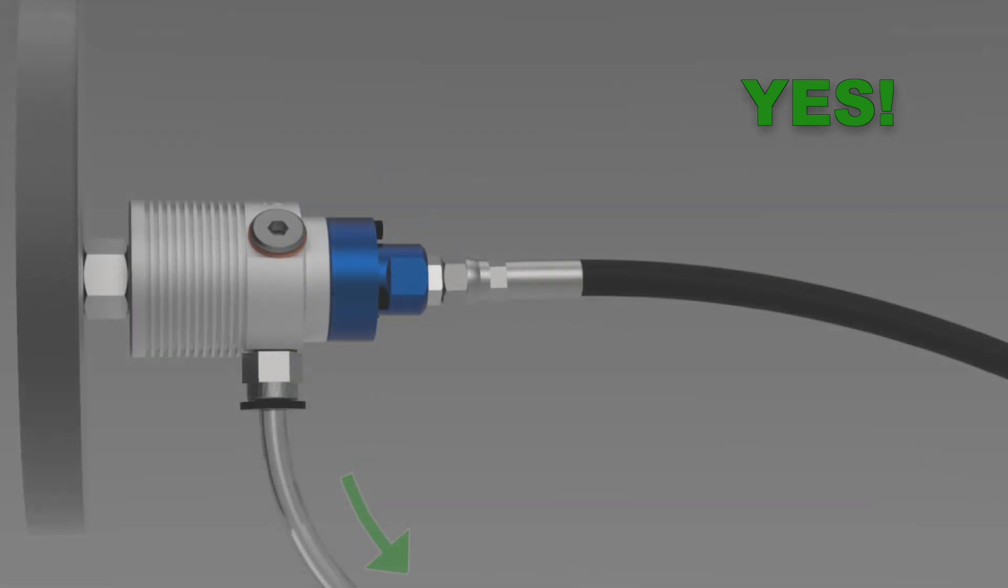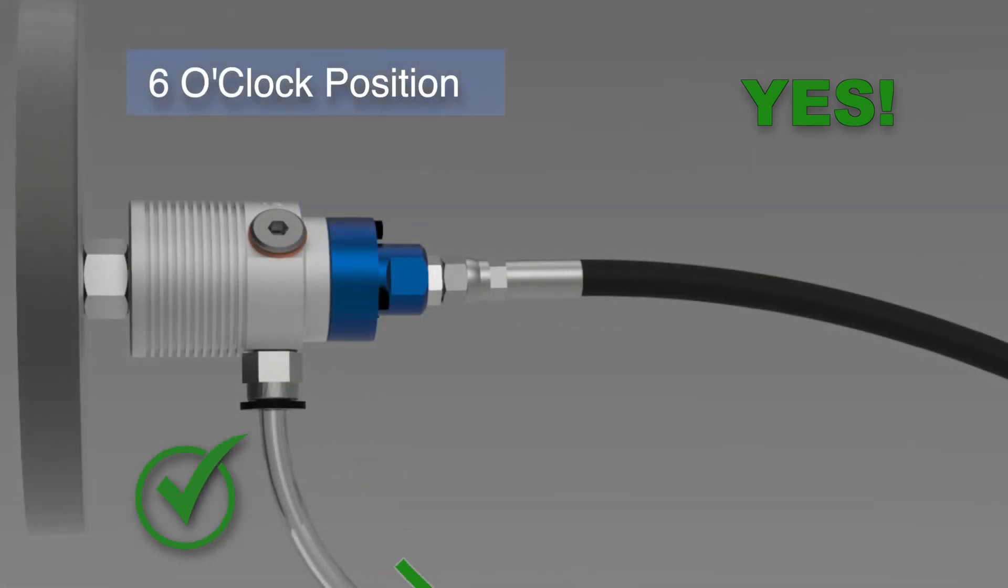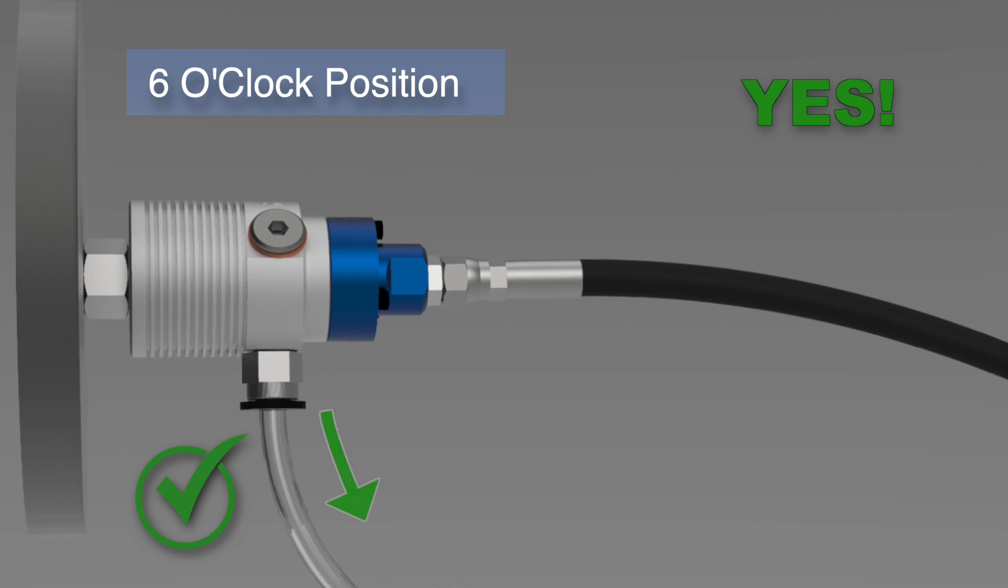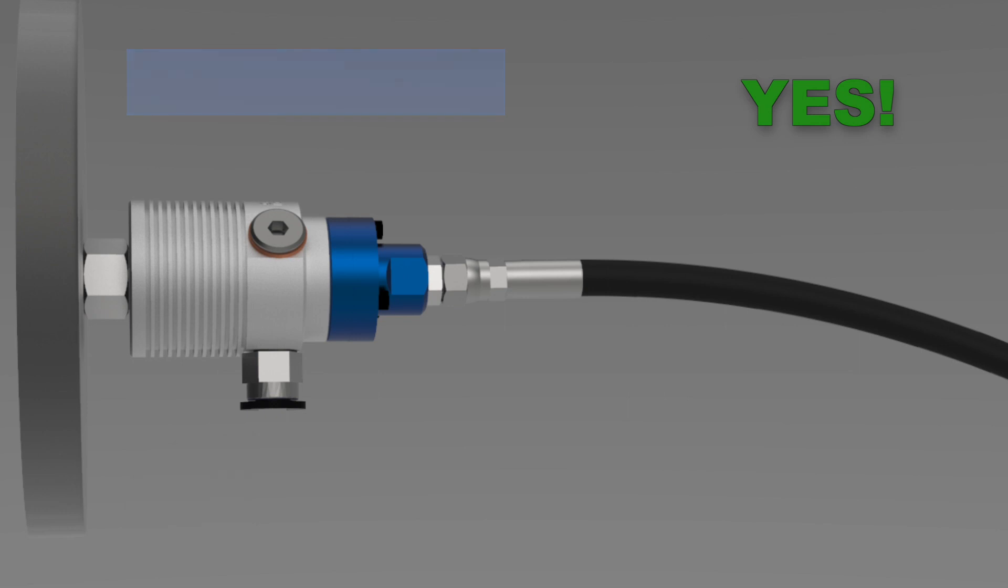In a horizontal installation, proper drainage requires the drain connection to be at a six o'clock position. The six o'clock position is essential even if no drain hose is used.